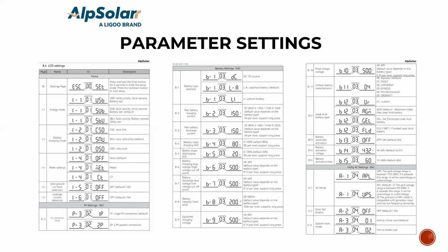as well. So let's say the first thing you are seeing there is the energy mode. What energy mode would you want to use? You see USB, you see SUB, you see SBU, depending on what source of power you want to use as your priority. If it is SUB, you navigate down to 1, which is our energy mode. Then you pick SUB, now click on enter, then navigate down to SUB, then press enter again to activate it as well. And every other setting that you want to make.